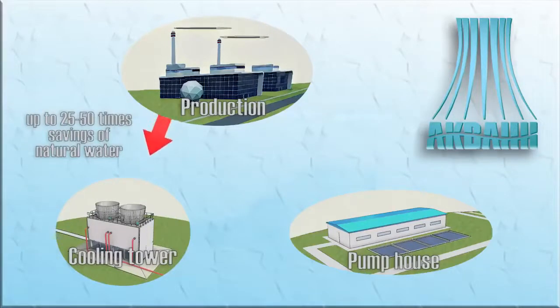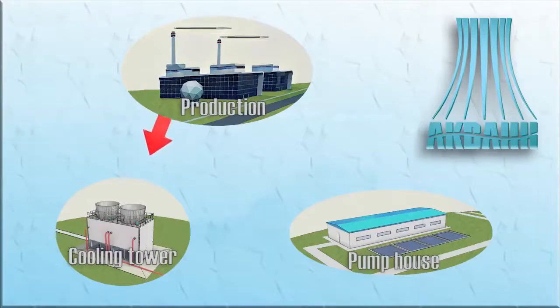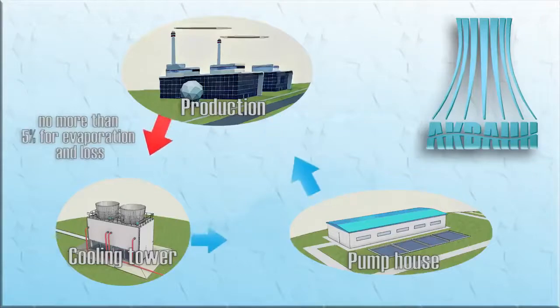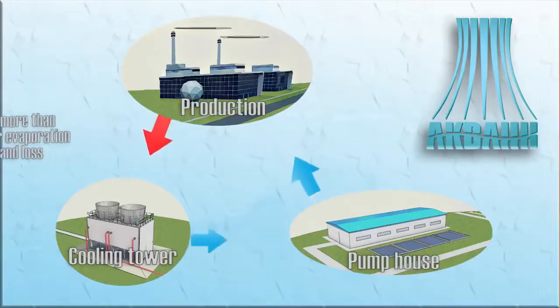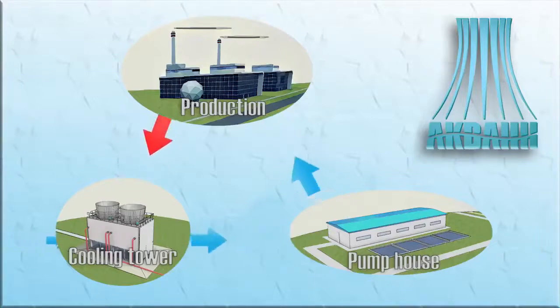After cooling, the main volume of recycled water is fed back into the process cycle. Usually no more than 5% of water is lost to evaporation, drip loss, leakage, and discharge into a blowdown system. Losses are replenished by freshwater makeup.